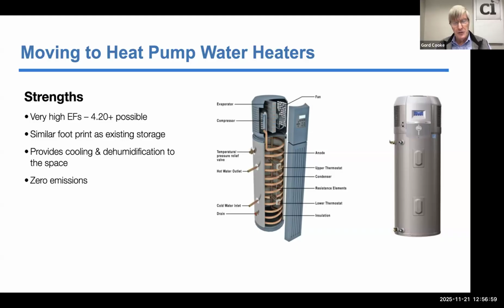You'd say that certainly makes sense in summer, because you're using the waste heat from your house, cooling the house while heating the hot water. But what happens in heating mode? If you're heating your house with a heat pump at 300% efficiency and heating the hot water at 300% efficiency, yes, you are cannibalizing heat from your house, but at the same efficiency, so it basically works at a factor of 1 in the wintertime.